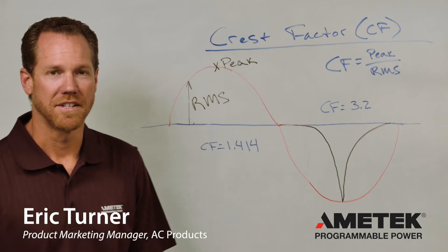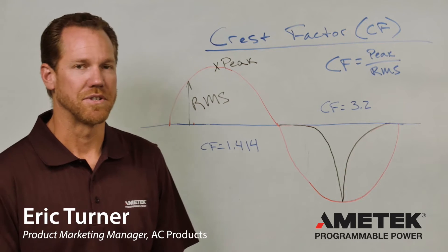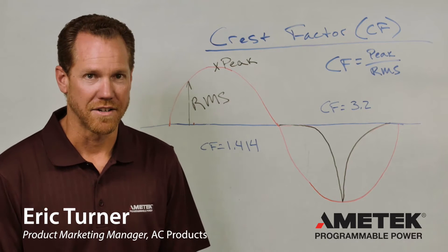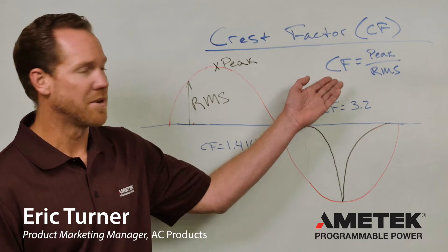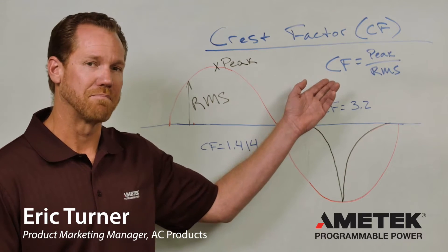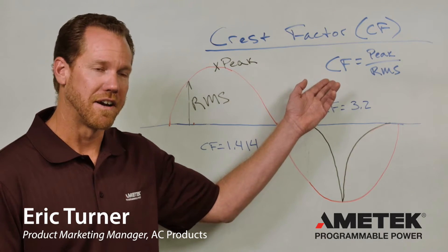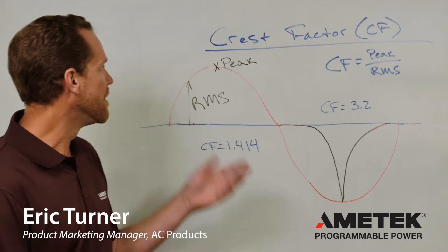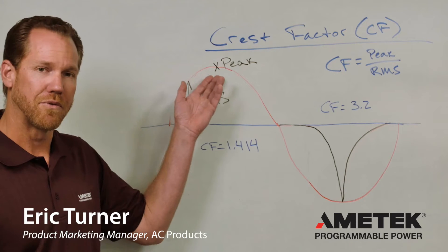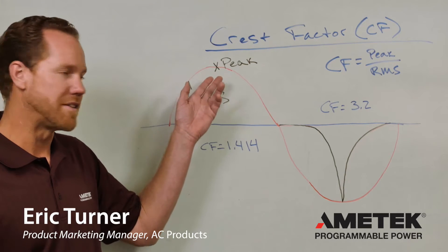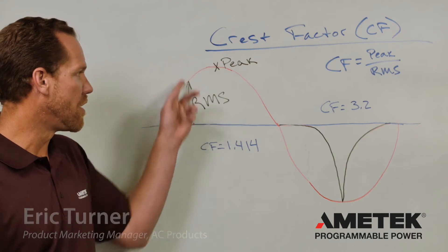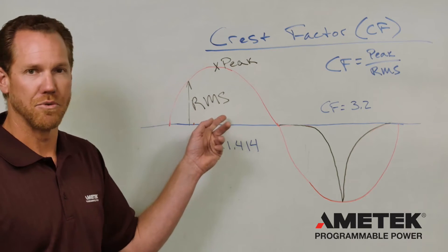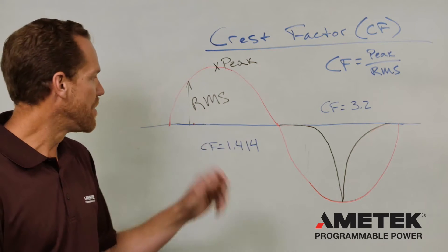A common question when selecting an AC power source is: what is crest factor? Crest factor is simply the relationship between peak current and RMS current. In a wave shape like this, you might have the peak here, and the RMS is the root mean squared value.